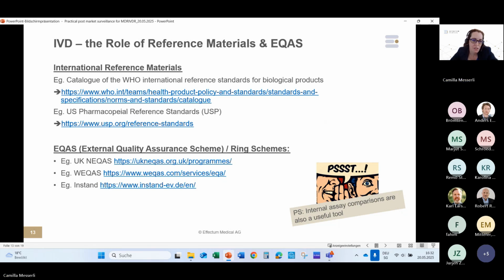And then you can actually test those in your quality control laboratory, or in the development laboratory, whatever, send in the results, and you then get a report, which anonymously, obviously, summarizes the data from all participants and the expected value that should have been obtained. And with that report, you can actually show that your standardization of your IVD assay is up to date. And this is something that you should definitely also include in your post-market surveillance reporting. So this would be post-market performance follow-up.